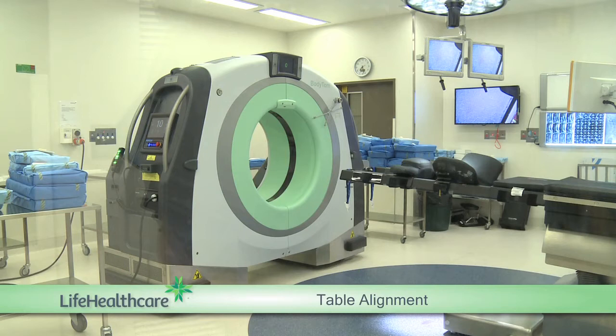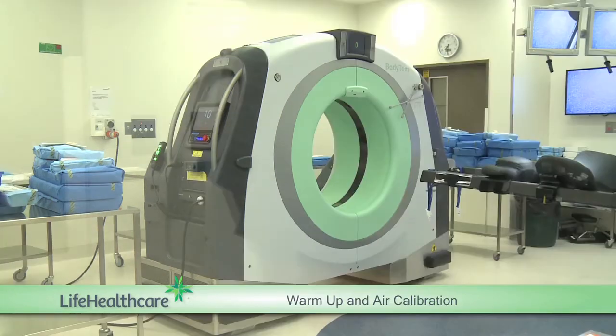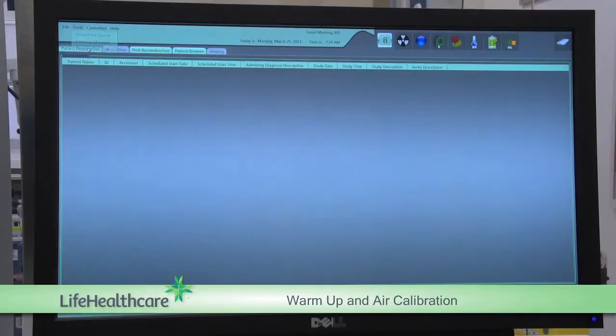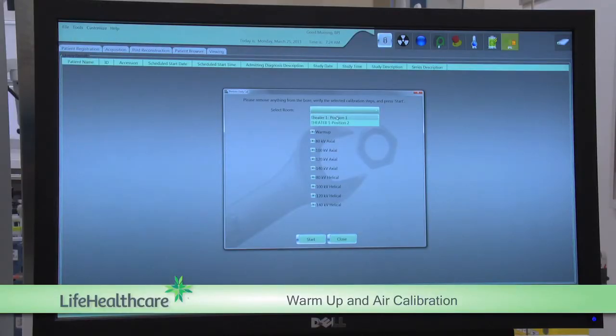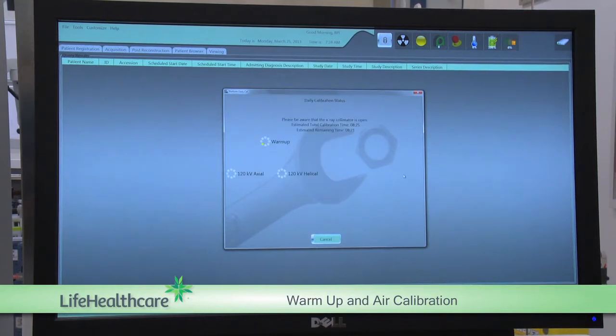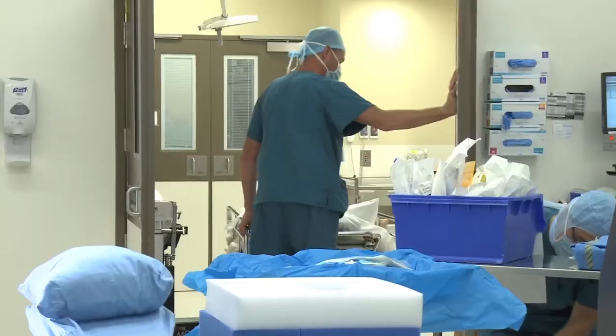The gantry is then parked in position approximately 1.5 metres from the end of the table using the caterpillar drive system. This is done to clear the surgical area of obstruction until the BodyTom is required for data acquisitions. Like all CT scanners, a warm-up and air calibration procedure is required. A full warm-up and air calibration takes roughly 8 minutes. This is performed at the beginning of the list to aid in workflow. A follow-up air calibration may be required later in the day. However, this short calibration only takes 2 minutes and can be performed when changing patients.